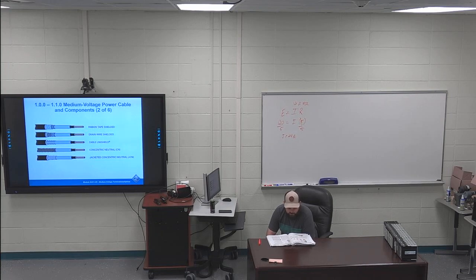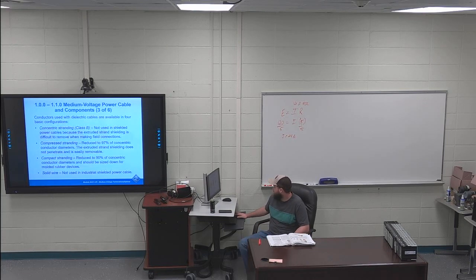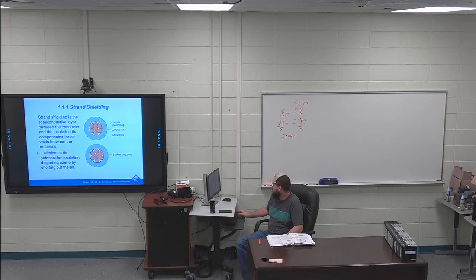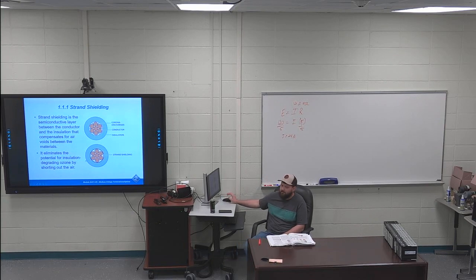Strand shielding is shown in figure 4. So you can see that over on page 3 on the bottom. You can see that strand shielding. Let's see if I've got strand shielding in this picture right here. It shows the shielding that's below that, and then if there's actual air in here, they can have corona discharges, but that strand shielding eliminates the potential for that.